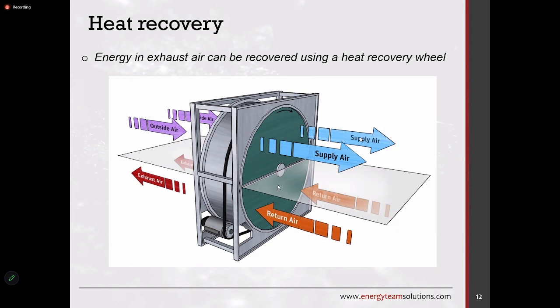So this is a kind of heat exchanger which will absorb the cool which is passed through the return air and bring it here to the supply air. So this wheel is rotating very slowly, so that there is enough time for the heat transfer to happen. It is absorbing, this particular material like a radiator fin kind of a thing. It absorbs the cool. The air systems are not mixed because the return air is highly polluted. It could be CO2, it could be carbon monoxide, it could be an odor. So they are not mixed, they are totally separated.